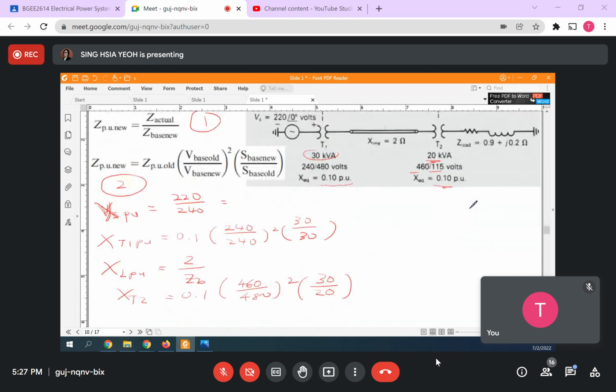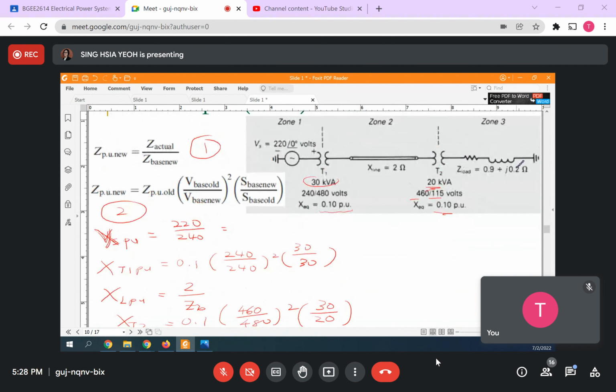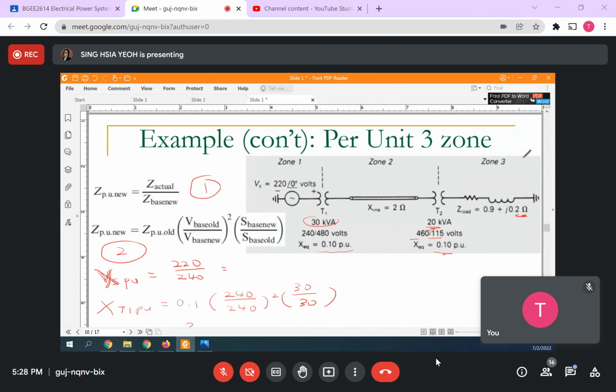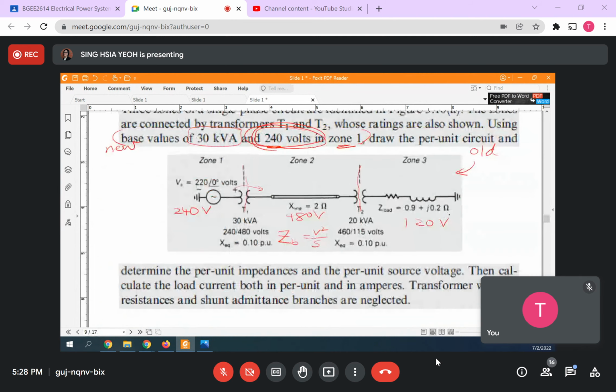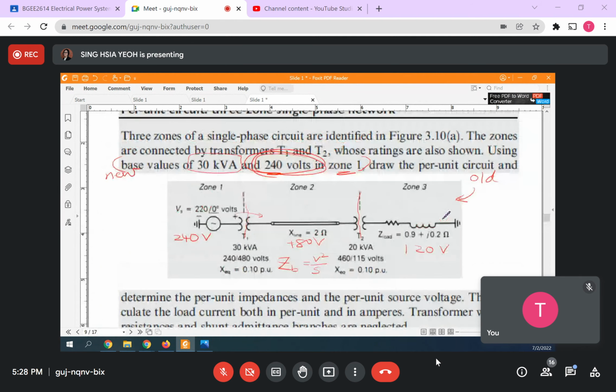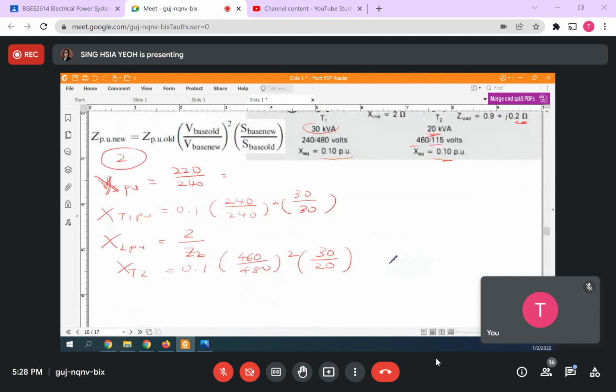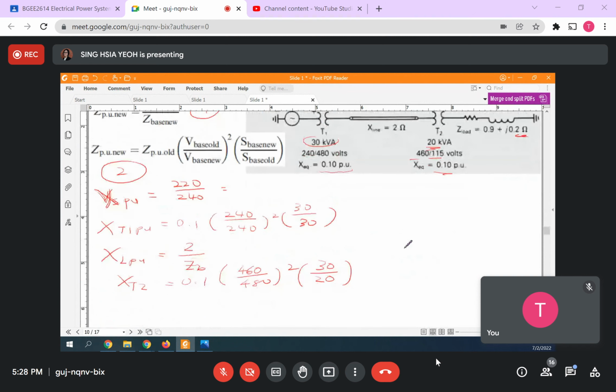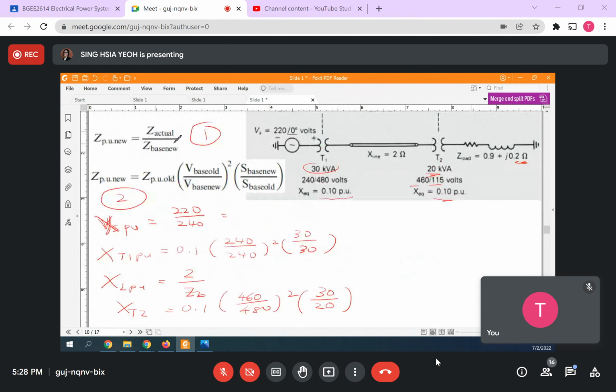So load here, same thing. Then this is in ohms, and the new value, base value, is in voltage. So that's why you need to use V squared over S. So now the V will be 120, because this area is 120. Then power 2 divided by S, 30K. So the load here, PU, also use equation 1, then divided by the Z base.